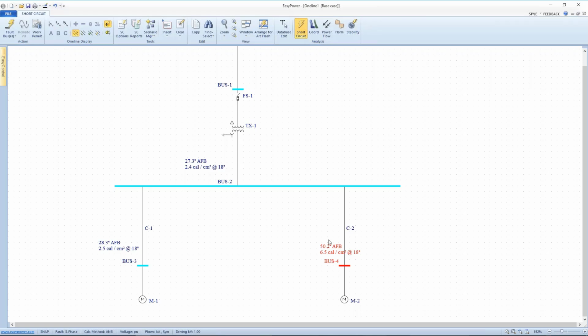If I walk down the road to this bus, the bus 4, my arc flash boundary is almost doubled, my incident energy is almost tripled, and now your tool's telling me I need to put on more PPE to work on this bus. What's wrong? I said, I don't get your point.